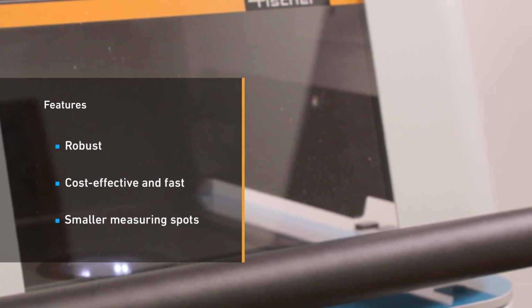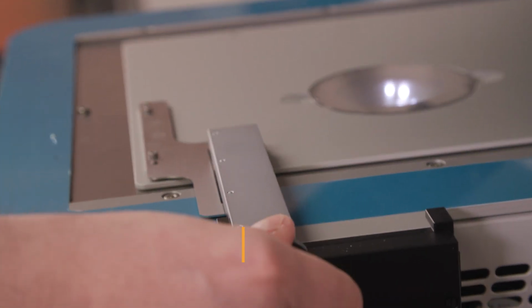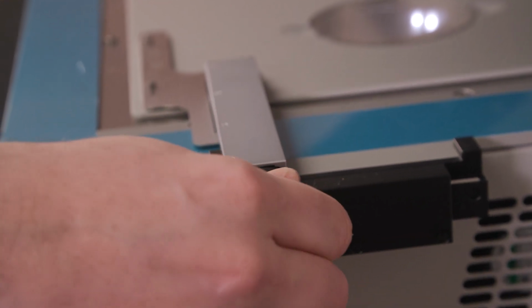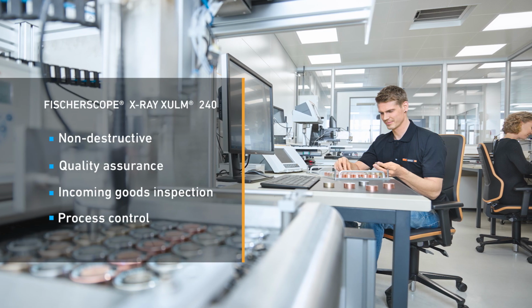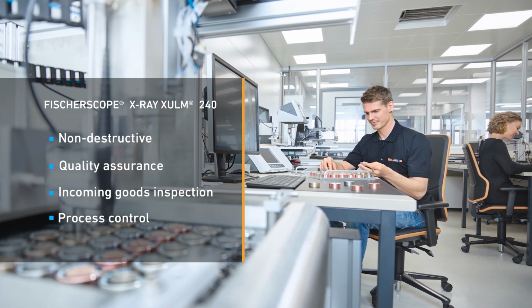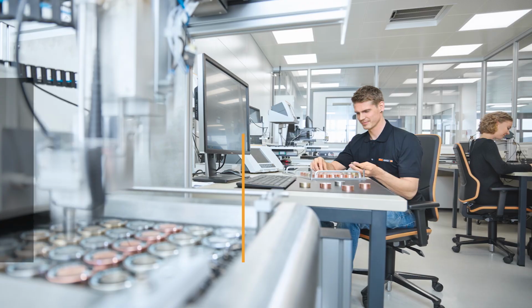Its main feature is a special microfocus tube, which means that it can be used for smaller measuring spots down to 0.1 millimeters in diameter. The instrument is well suited for measurements in quality assurance, incoming inspection, and process control.